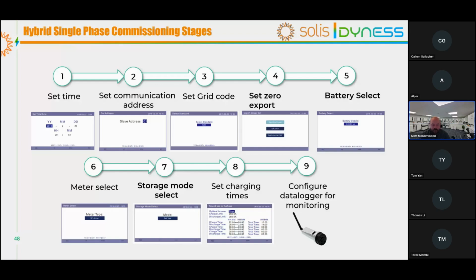Once you've then set up the inverter, we would always suggest that you have a data logger installed, which means that it goes to Solis Cloud, which in turn means that if you have any issues, that you can contact our service department, give them the plant ID, or give them the data logger serial number, or even the inverter serial number. We can search that through Solis Cloud, and then we can also do some remote fault finding, etc.